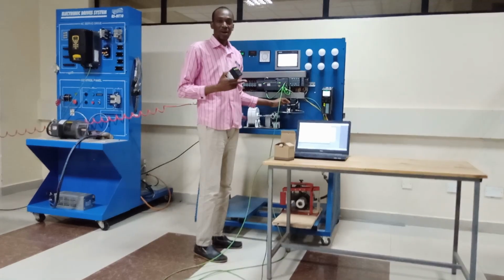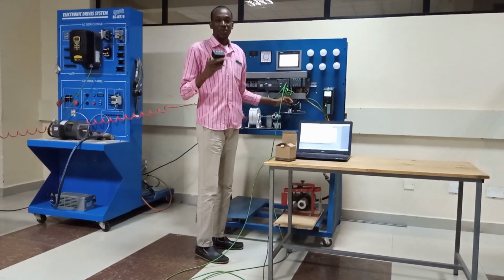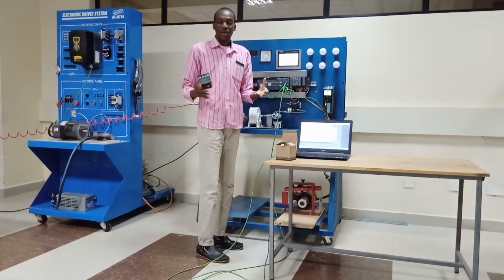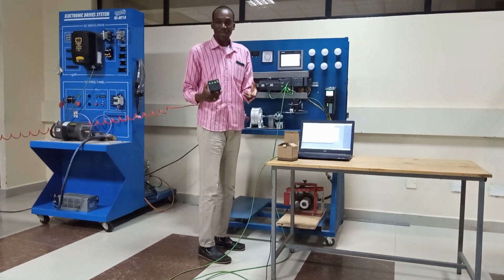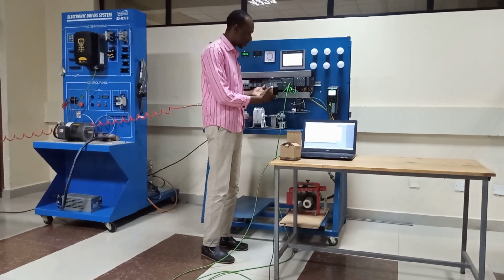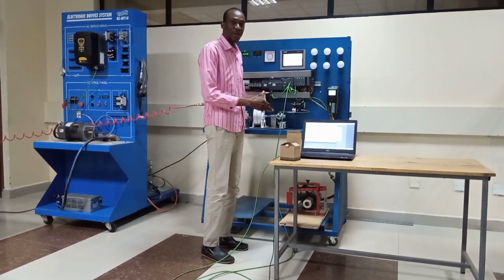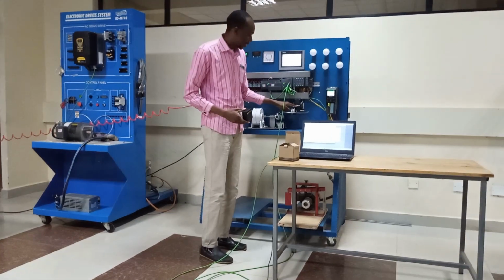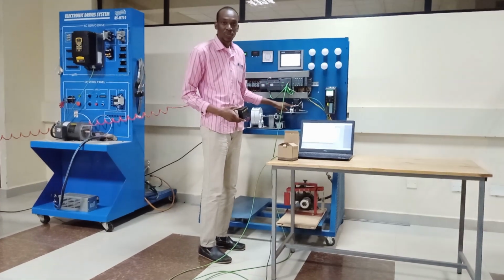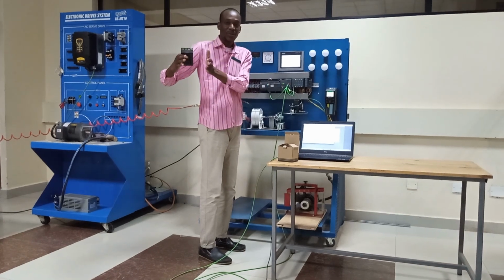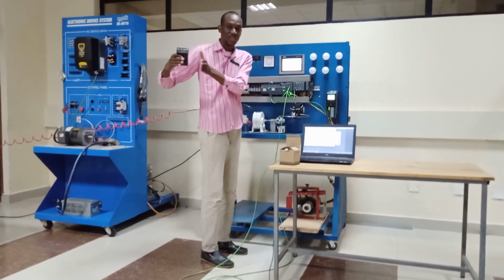Then to set the IP converter, there are 2 ways. First, we can use an ammeter. With the ammeter, you measure the output current from the PLC. You connect it to the IP converter, and you can easily set your output using this span and zero to set the range from 3 psi to the value of the pressure you want, the maximum value of pressure you desire.